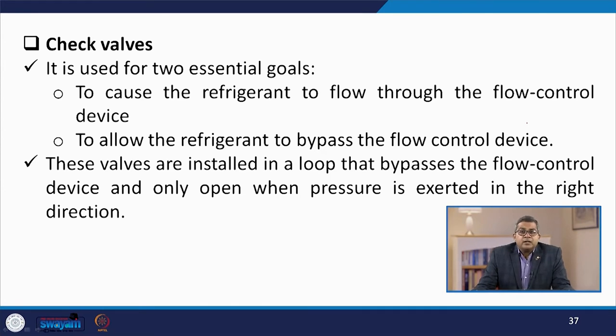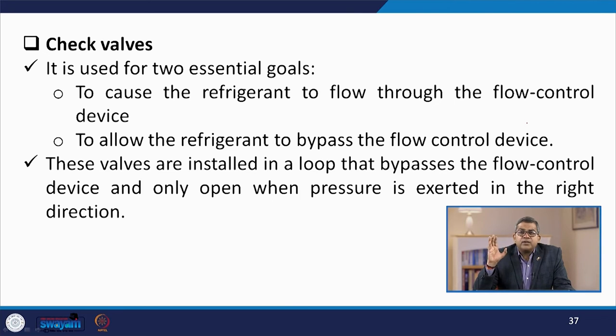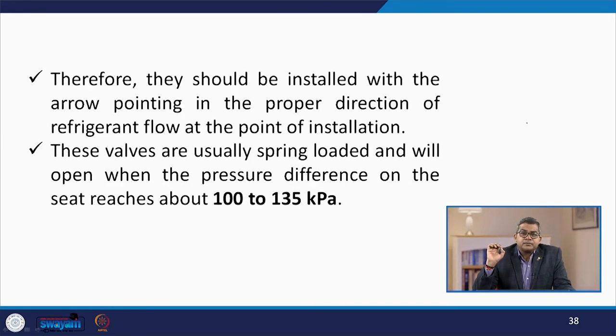The check valve is used for two basic essential goals: one is to cause the refrigerant to flow through the flow control device, and the second is to allow the refrigerant to bypass the flow control device. These valves are installed in a loop that bypasses the flow control device and open only when pressure is exerted in the right direction. They should be installed with the arrow pointing in the proper direction of refrigerant flow at the point of installation. These valves are usually spring loaded and open when the pressure difference on the seat reaches around 100 to 135 kilo Pascal.